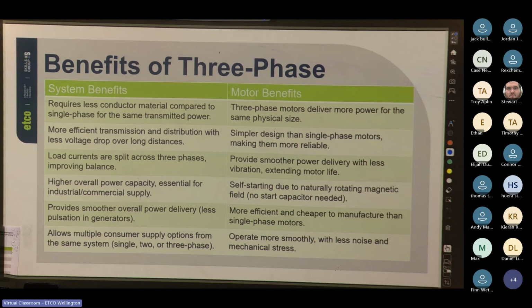Cool. So in star, one end of each winding is joined together at a common point called the star point. This gives us our neutral conductor, creating a four-wire system. In delta, each winding is joined end to end in a triangle shape. This gives us a three-wire system with no neutral. So if we were to draw them out on the board.